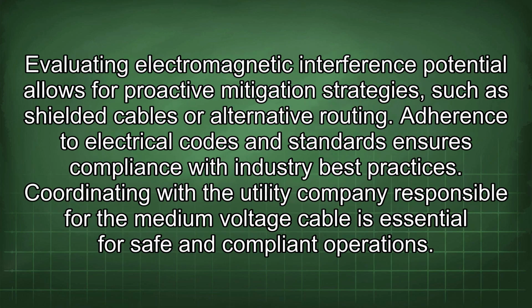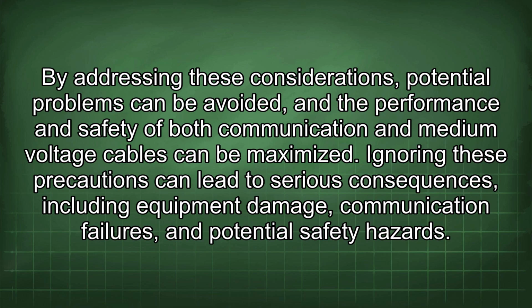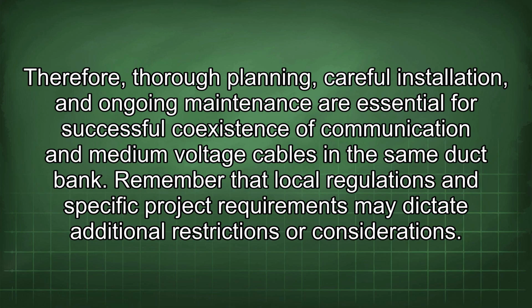Evaluating electromagnetic interference potential allows for proactive mitigation strategies such as shielded cables or alternative routing. Adherence to electrical codes and standards ensures compliance with industry best practices. Coordinating with the utility company responsible for the medium voltage cable is essential for safe and compliant operations. By addressing these considerations, potential problems can be avoided, and the performance and safety of both communication and medium voltage cables can be maximized. Ignoring these precautions can lead to serious consequences, including equipment damage, communication failures, and potential safety hazards. Therefore, thorough planning, careful installation, and ongoing maintenance are essential for successful coexistence of communication and medium voltage cables in the same duct bank.